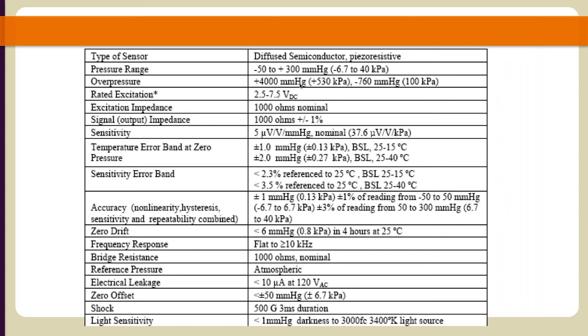For overpressure ranges, your setup would be different — you would require a low-voltage amplifier and a data acquisition unit to obtain pressures using the Microcath. You would also need to use a multi-point calibration. The calibration would be a little more involved than the straightforward two-point calibration used in the linear range, but it is definitely doable.